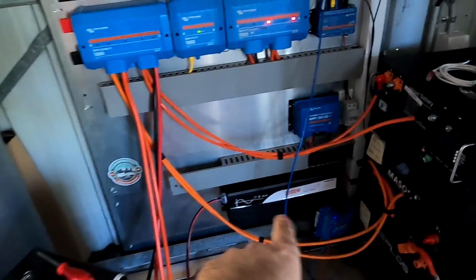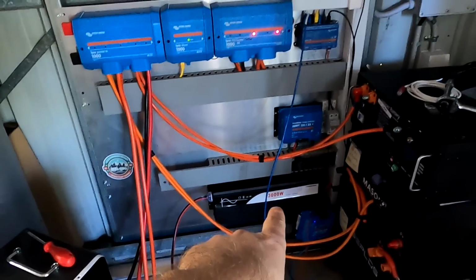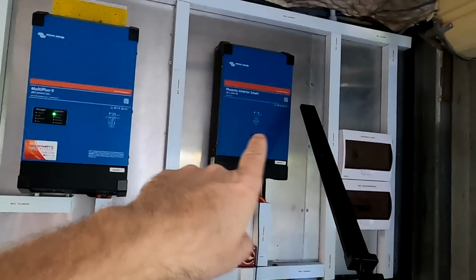Perfect. So this afternoon we want to do a high amp discharge test. Well, it's not a super high discharge test, but at least as high as we can go. We have 2 inverters connected: the Xia inverter down here at our Powerwall 2.25, and we can also turn on the Phoenix inverter, both supplied from our Frankenstein battery. We'll probably get around 110, 120 amps maximum. So this will be our high amp discharge test.